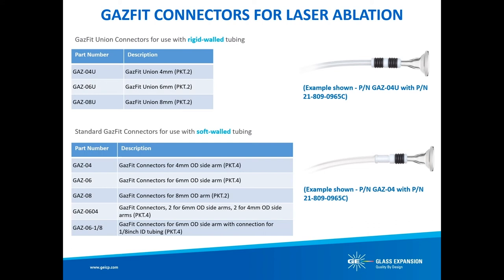Two tables are listed for Gas-Fit connectors. The first is the union-type Gas-Fit connector, used when connecting rigid wall tubing from your laser ablation system to one of the torch adapters — the Gas-Fit union provides a push-fit seal of the laser ablation tubing directly to the torch adapter (e.g., part number GAZ-04U with adapter 21-809-0965C and 4mm OD rigid wall tubing). The second table lists standard Gas-Fit connectors for soft wall tubing, where the tubing pushes over a barb to seal to the Gas-Fit connector, which then slides over the arm of the torch adapter (e.g., part number GAZ-04 with adapter 21-809-0965C).